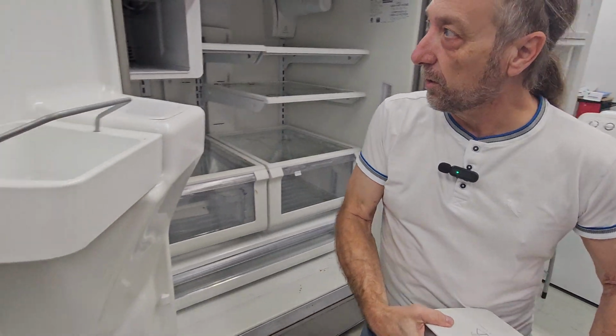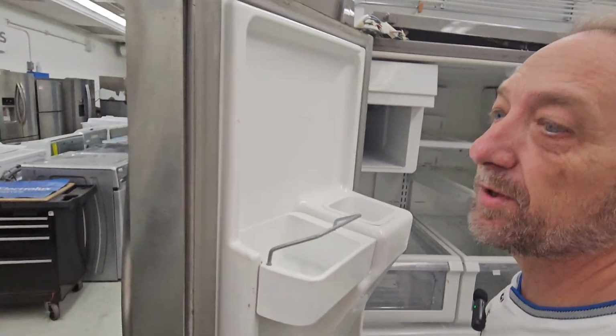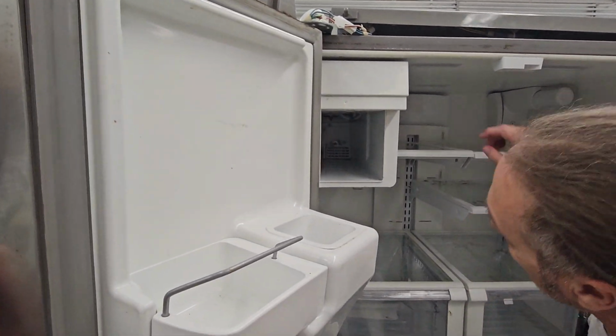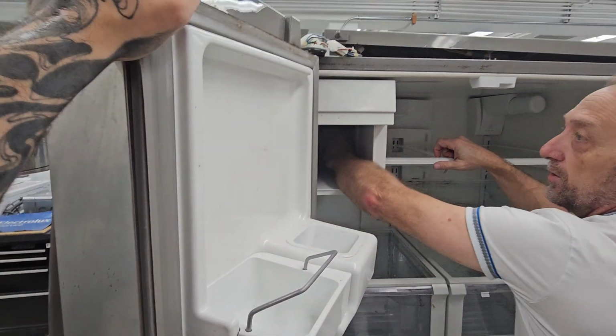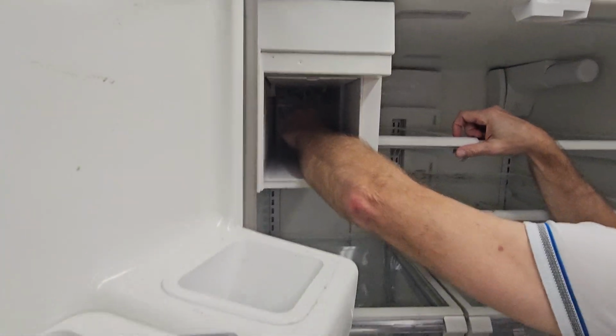I'm not going to take this whole assembly out, but look at this wire I've got my finger on. That's the flex tray, and this wire is the sensor on the bottom of that tray, the tray sensor. It's this white wire right here, and it goes to the bottom of the tray. A lot of times that sensor falls off into the bucket, and then the ice maker doesn't know to drop the ice.